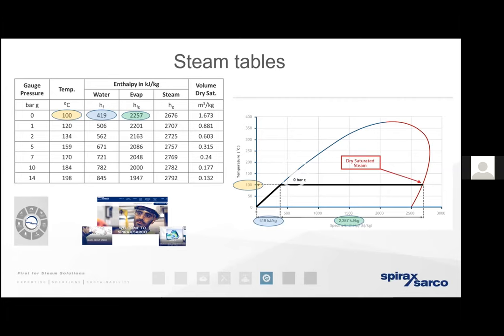Steam passing across that trapped mass of condensate will have more and more of its energy sucked out — it gets wetted out. The biggest problem with wet steam is that the mass reaching the process will have significantly less energy. The heat exchanger will either have to consume more and more steam to provide the required heating effect, or it will be effectively undersized, meaning the process time will extend and extend.